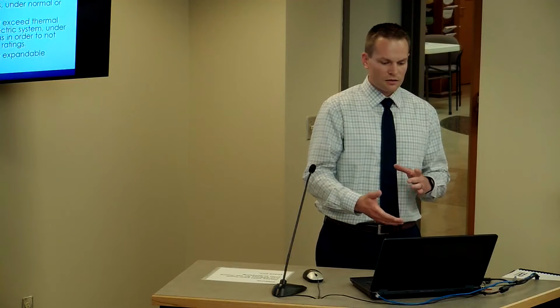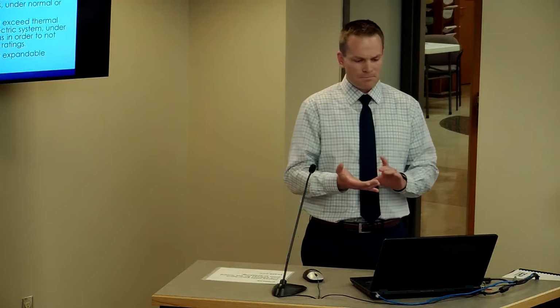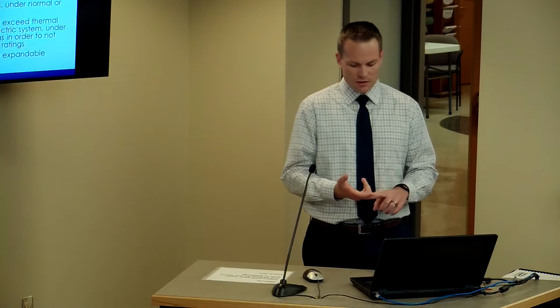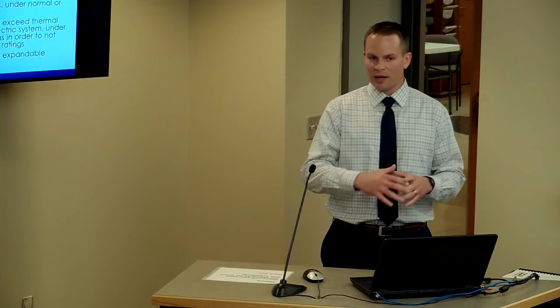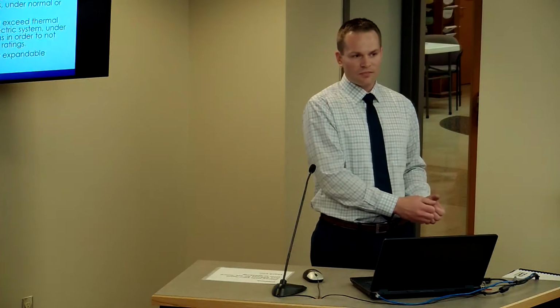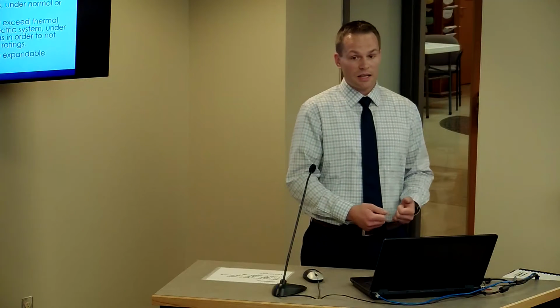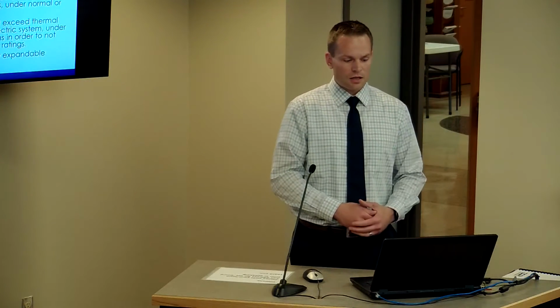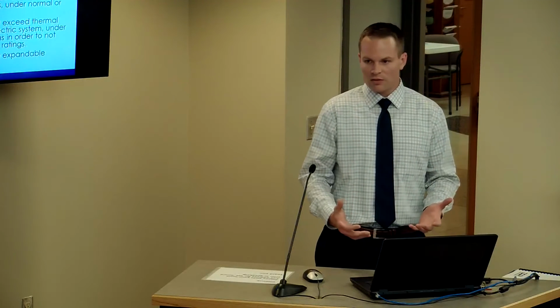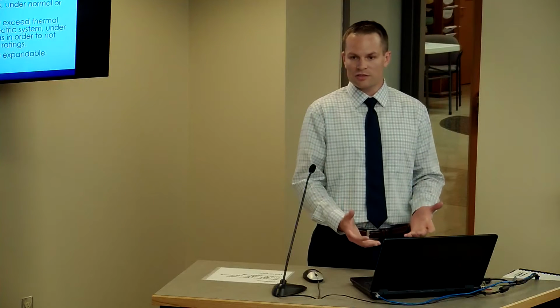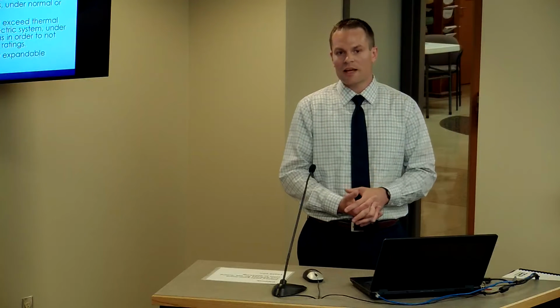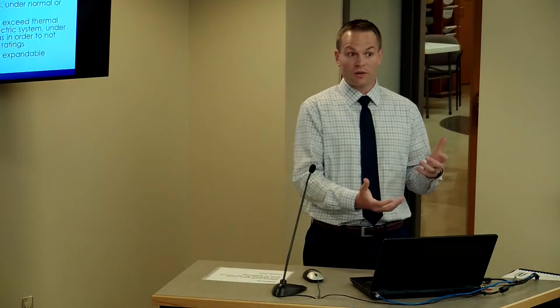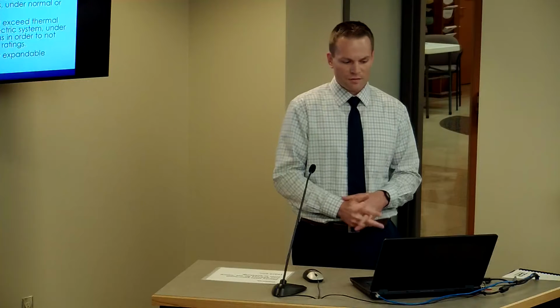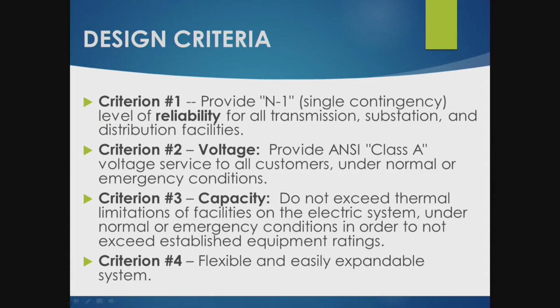There are four criteria that we try to meet. One is on the reliability side: N-1 contingency. If you lose any one piece of equipment, you need to be able to back that piece of equipment up in an efficient and reliable manner. We also need to maintain a certain voltage level consistent with ANSI and industry standards, within certain voltage bands that are likely to fluctuate during that event. So if you need to back up a feeder in the system, it needs to be able to provide the same voltage in the backfeed emergency situation as it can in its normal state.